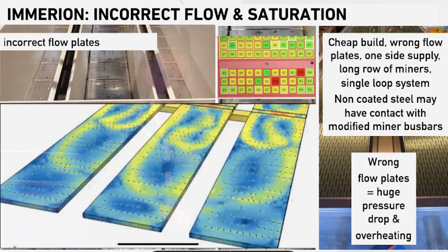The biggest problem with immersion systems or immersion tanks is proper saturation. Current miners require twice the flow of the previous generation. If you were immersing an S19 miner at 3.5 kilowatts, and now plan to immerse something like an M56 miner at 6 or 7 kilowatts, you need to provide enough flow and fully saturate the miner, otherwise you'll fail.